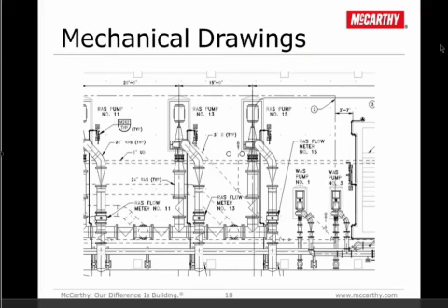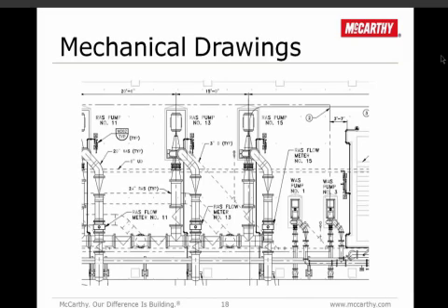The mechanical drawings, as we all know, show the mechanical installations, the equipment, the flow meters, seal water requirements. So the mechanical drawings here, like I said, have seal water. Not only in our checklist will we have verification of the pressure gauges, we can identify that early during the design and the shop drawing approval so we can quantify that and verify during the equipment installation that we have the right materials in the right place, that we have proper seal water, lubrication, and controls for that equipment.